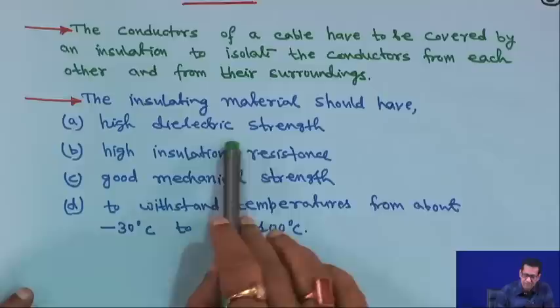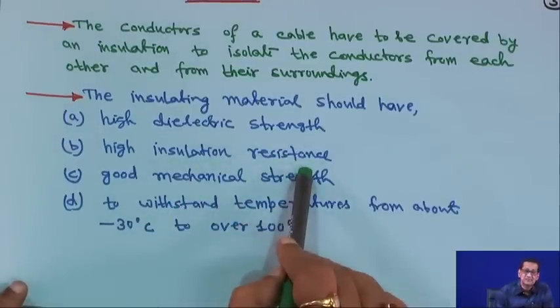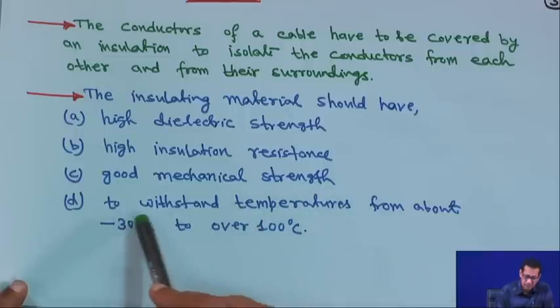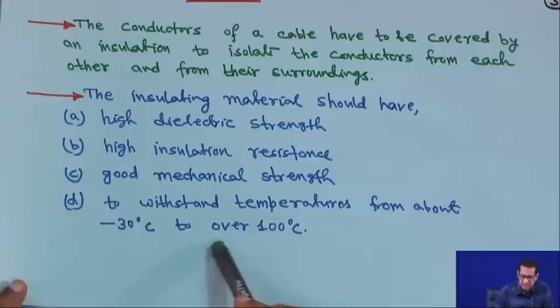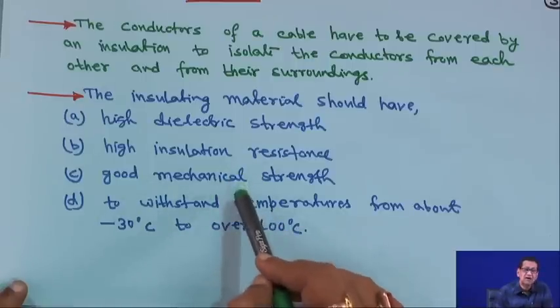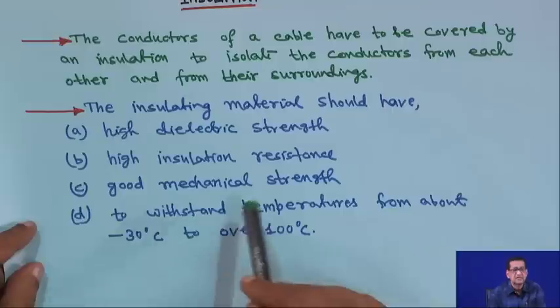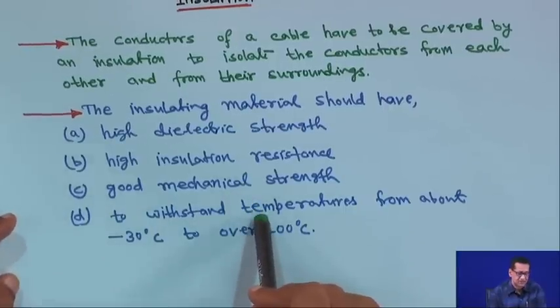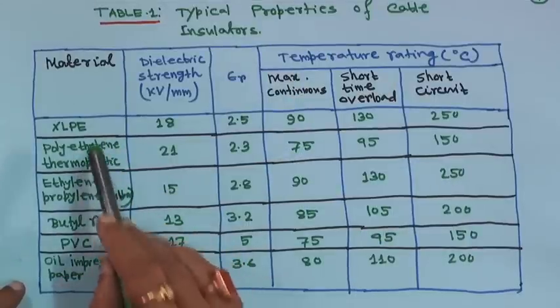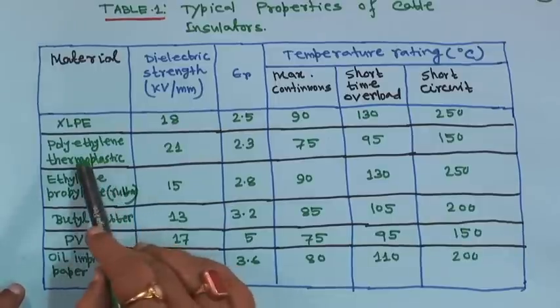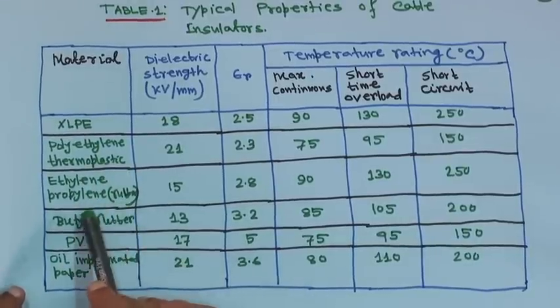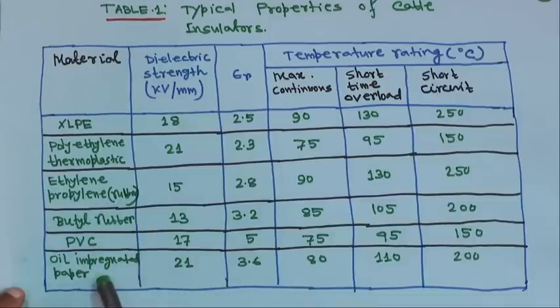The insulating material should have: high dielectric strength, high insulation resistance, good mechanical strength, and the ability to withstand temperatures from about −30°C to over 100°C. Typical cable insulation materials include XLPE, polyethylene thermoplastic, ethylene propylene rubber, butyl rubber, PVC, and oil-impregnated paper.